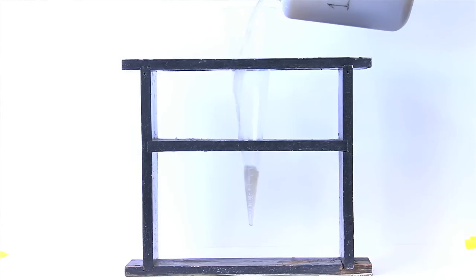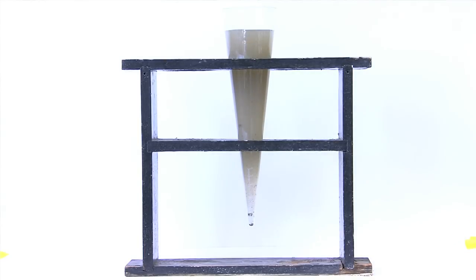Like a stream or river, the water coming to the wastewater plant is constantly moving — flowing out of a building, flowing downhill in drains, eventually reaching our influent pumps where it's pumped uphill to the head of our plant. When the wastewater reaches a primary settling tank, it finally has a chance to slow down. This is a sample of our influent being poured into an Imhoff cone — something we do three times every day. We measure how much settleable solids end up in the bottom of the cone after one hour of settling. This is a time-lapse version so you can see what happens in the first 10 minutes or so.